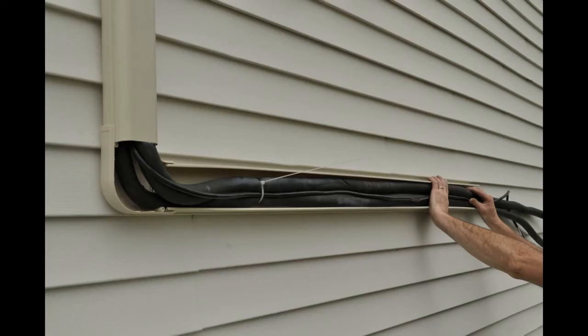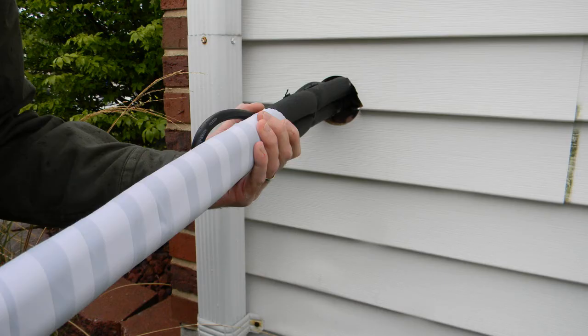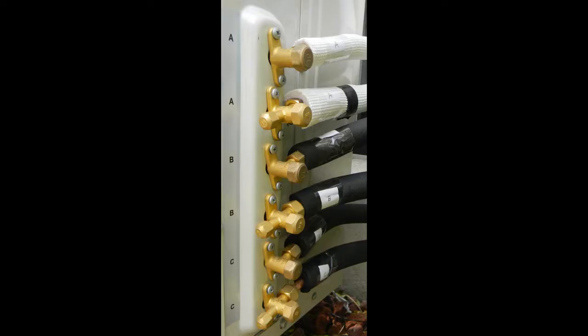Use multi-stranded copper wires of the correct type and gauge for your power connections. Use an uncut length of wire. YMGI does not recommend splicing wires in line. Use cable ties and pipe band to bundle the copper line and wires with the condensate hose being laid at the lowest position to avoid any possible kinks or sags. Extend the drain hose if needed. The method for securing the wrapping tape will be detailed in another video.